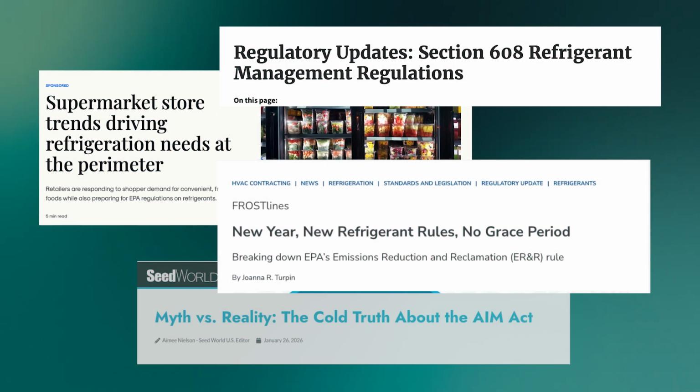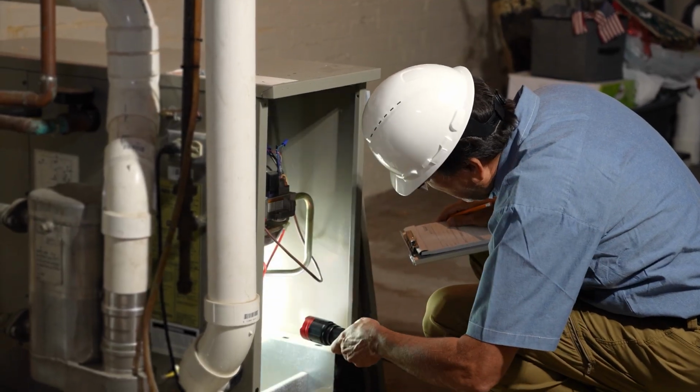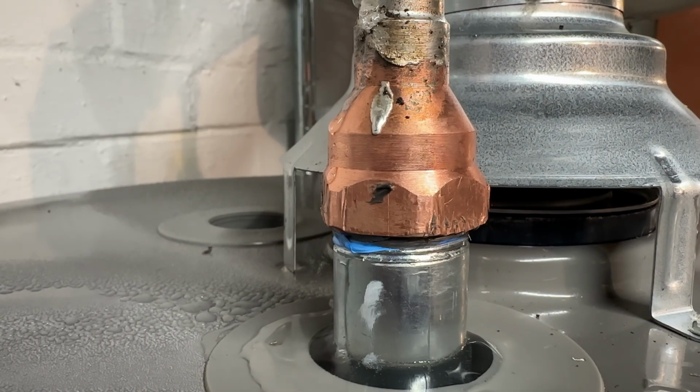One key reason, obviously, is regulation. These regulations began with EPA Section 608 under the Clean Air Act. They've since been expanded under the AIM Act to more asset types and more material types. And many states have their own specific regulations, whether it's in California, New York, Washington, all focused on helping operators manage and reduce refrigerant leaks by instituting a set of best practices to ensure that whenever an asset is serviced, you are tracking the key components that contribute to refrigerant leaks, and you're measuring them so that you can ultimately reduce the leaks in your system.